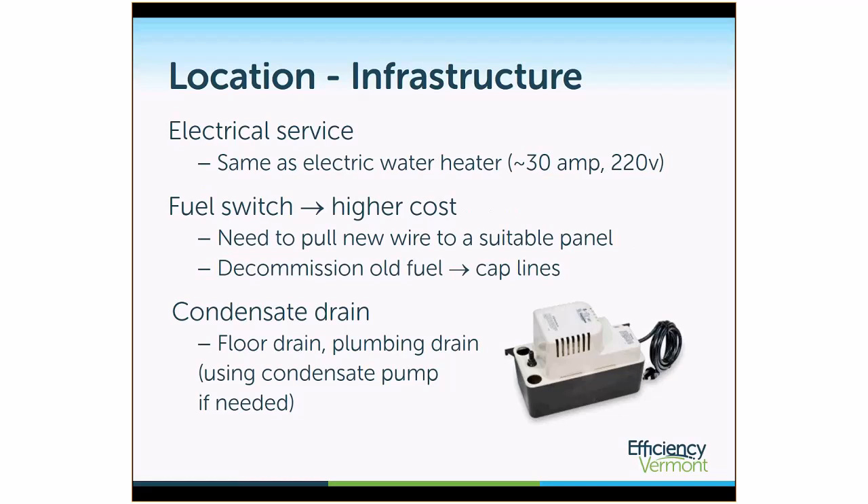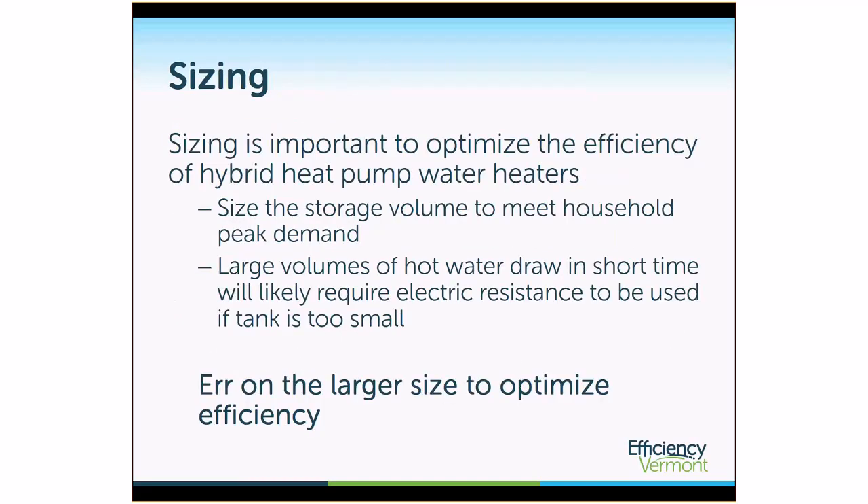Oftentimes a condensate pump is needed to pump the condensate up to where that plumbing drain might be. Sizing is not the same as just replacing a 40-gallon tank with a 40-gallon tank. It's important to optimize the efficiency of a hybrid heat pump water heater by sizing the storage volume to meet the household's demand. Large volumes of hot water drawn in a short time will likely require electric resistance if the tank is too small. Erring on the larger size will optimize efficiency so the unit can run in heat pump mode more often.